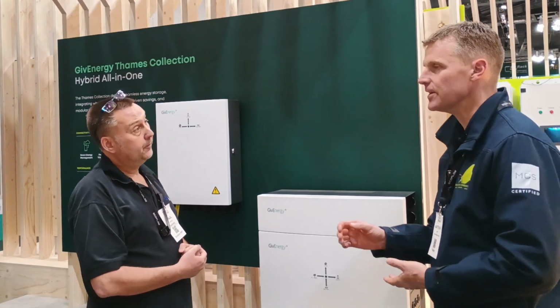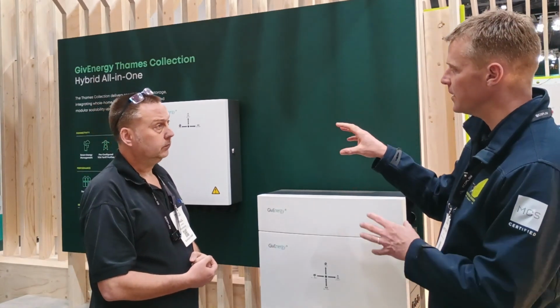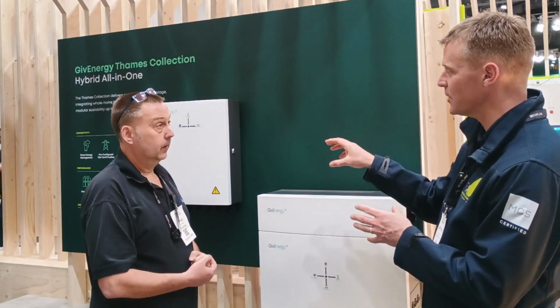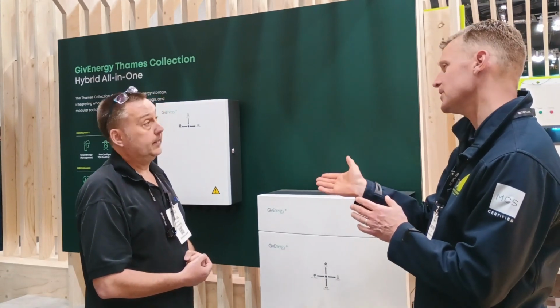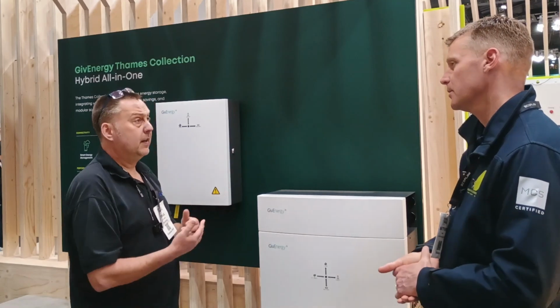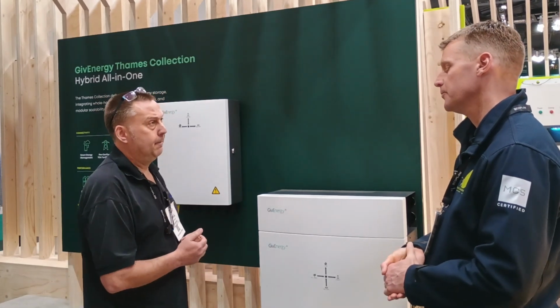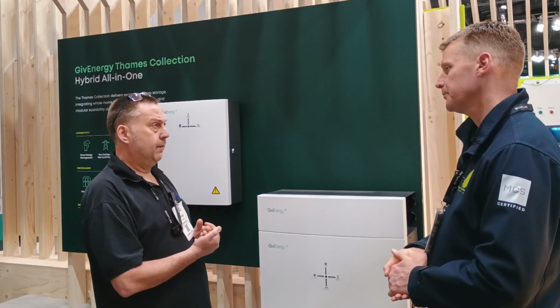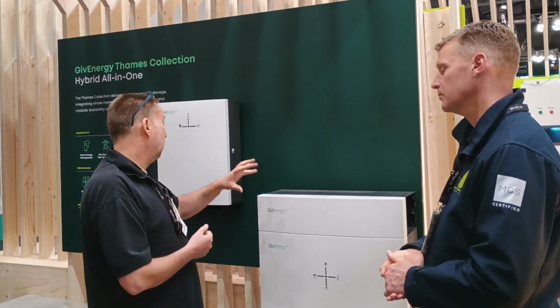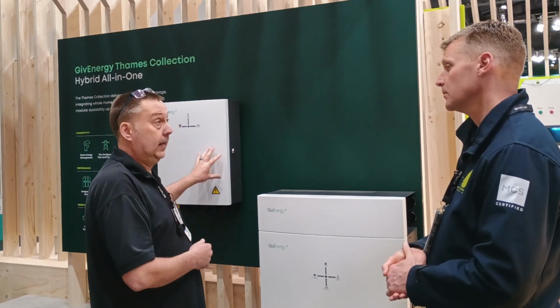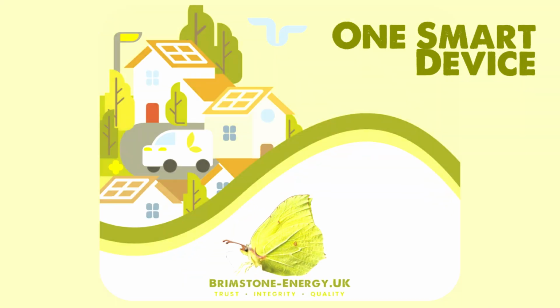Okay. So just so I understand that correctly, we'd have to wire into the main circuit within the house, a specific circuit that's taking that up. So you would bring it from, usually a water heater would be the typical example. Instead of using a water diverter with a CT clamp, you would wire the immersion heater itself directly into here and switch it on and off with a smart load.